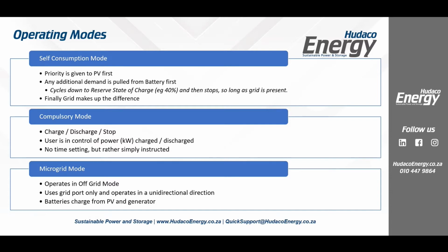And then finally, microgrid mode. In this mode, the inverter does not ever enter on-grid mode. It operates completely in off-grid mode. It uses the grid port only, and operates in a unidirectional manner. Your batteries can charge from PV or generator, but your loads are not fed from grid. They're only fed from the inverter. You would do that if, let's say, you're living on a farm, you've only got solar power, and there's no grid attached whatsoever. Then you go into microgrid mode. It stops looking at the meter for a voltage reference, and the inverter will always create the voltage. It always stays in off-grid mode.